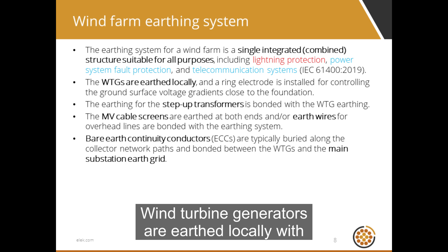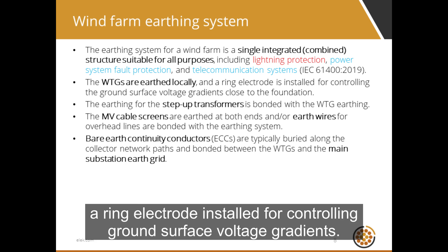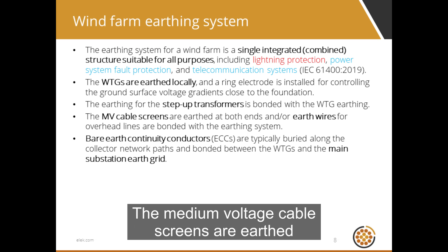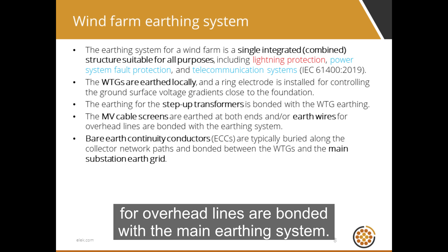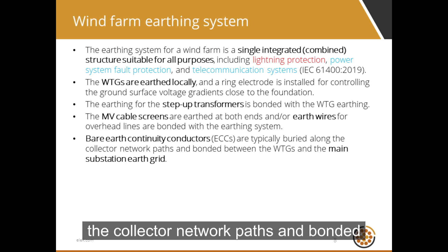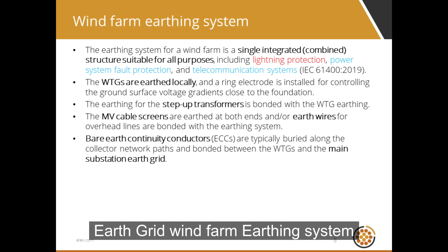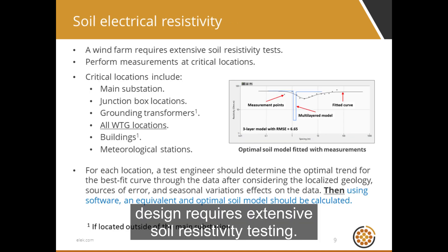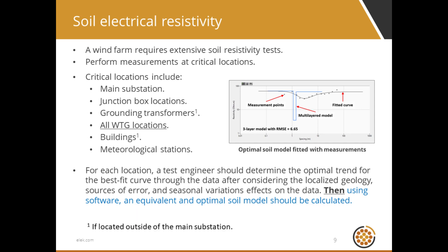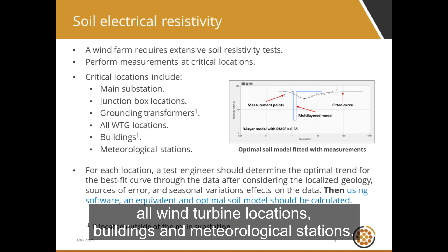Wind turbine generators are earthed locally, with a ring electrode installed for controlling ground surface voltage gradients. The earthing for the step-up transformers is bonded with the wind turbine earthing. The medium voltage cable screens are earthed at both ends, and earth wires for overhead lines are bonded with the main earthing system. Bare earth conductors are typically buried along the collector network paths and bonded between the wind turbines and the main substation earth grid. A wind farm earthing system design requires extensive soil resistivity testing performed at critical locations, including the main substation, junction boxes, grounding transformers, all wind turbine locations, buildings, and meteorological stations.